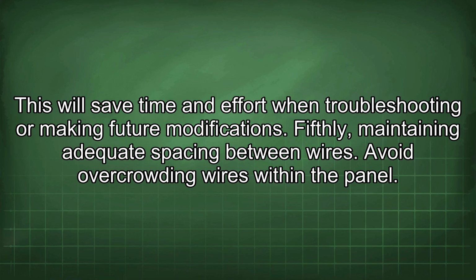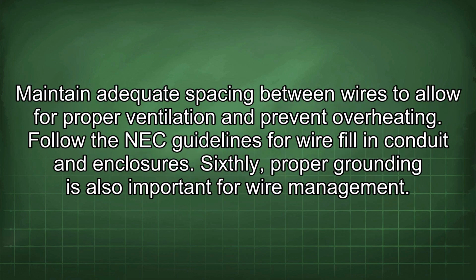Fifthly, maintaining adequate spacing between wires. Avoid overcrowding wires within the panel. Maintain adequate spacing between wires to allow for proper ventilation and prevent overheating. Follow the NEC guidelines for wire fill in conduit and enclosures.